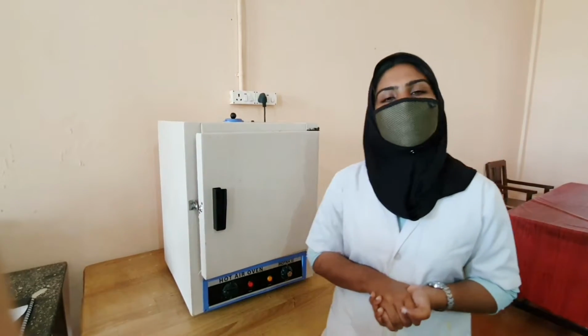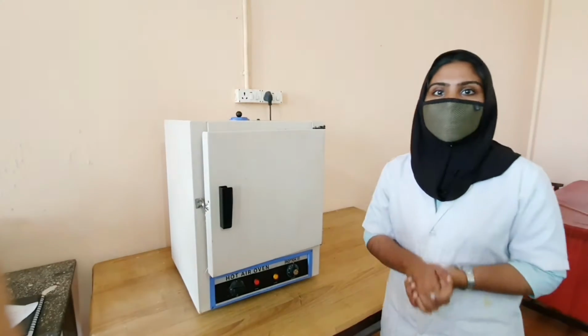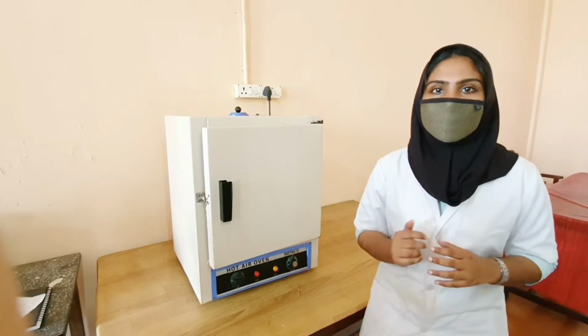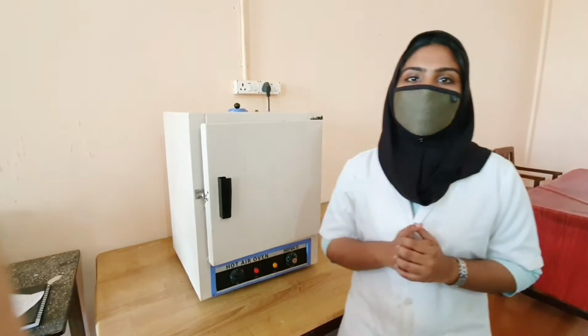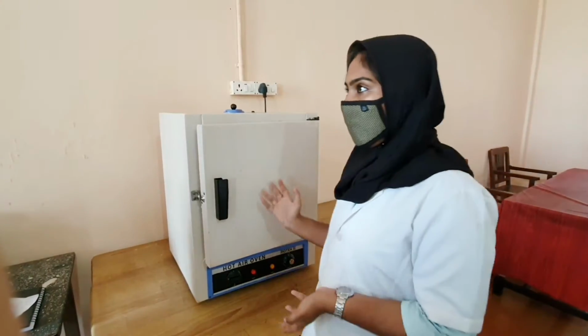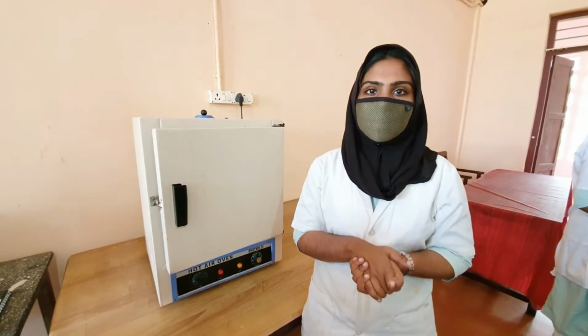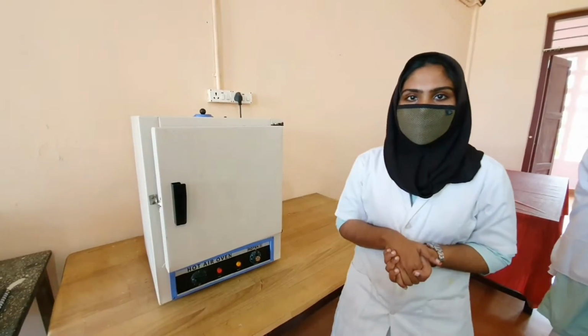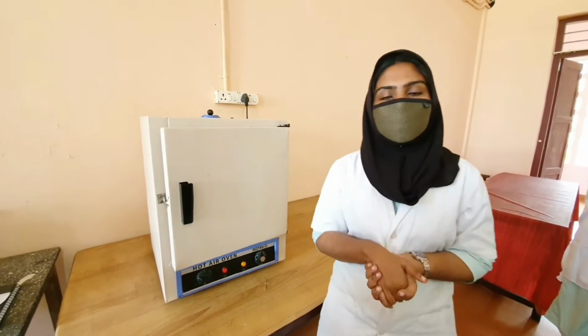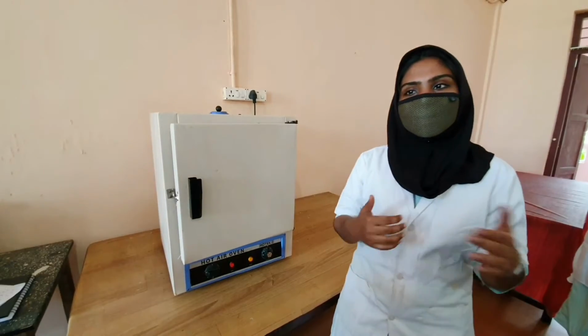We can sterilize glassware like flasks, pipettes and test tubes, powders like starch, zinc oxide and sulfadiazine, materials that contain oils, and metal equipment like scalpels, scissors and blades by using a hot air oven. The widely used temperature-time relationships in hot air ovens to destroy microorganisms are 170 degrees Celsius for 30 minutes, 160 degrees Celsius for 60 minutes and 150 degrees Celsius for 150 minutes.